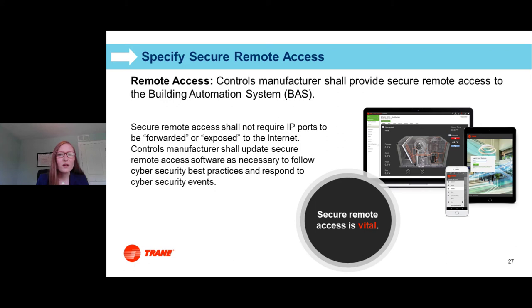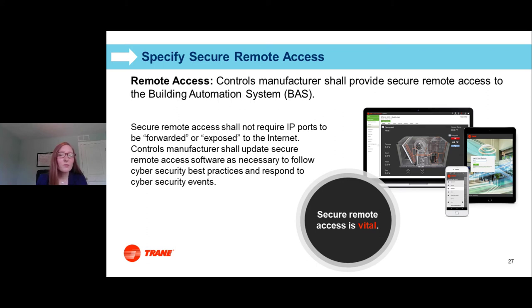Secure remote access: today clients need to understand their buildings remotely and access them from outside the building. This can be a point of contention between IT staff and building operators. We recommend working with your clients to understand how they'll get access to their system and specifying a method preferred by IT staff. Options include VPN, virtual private networks, cell routers, and even BAS manufacturer standardized solutions that keep systems off the open internet, really protecting the client's system and data.